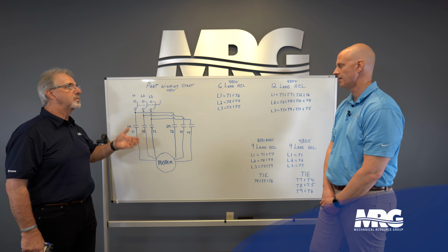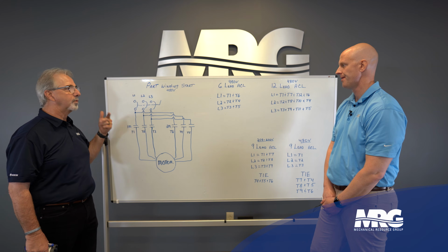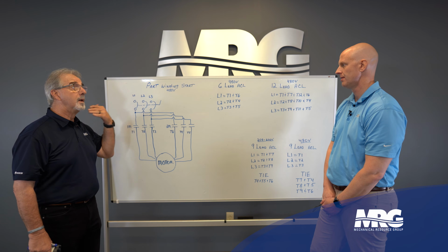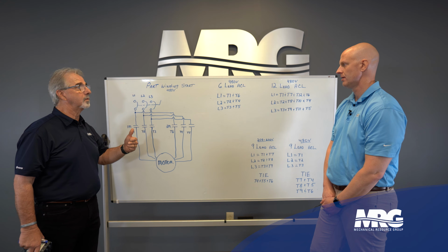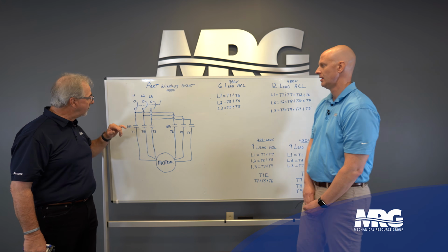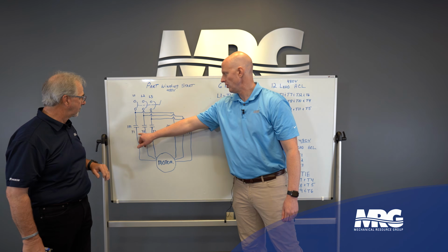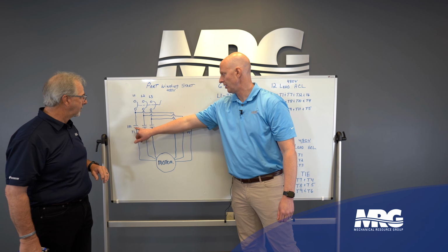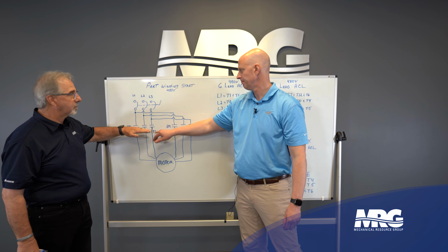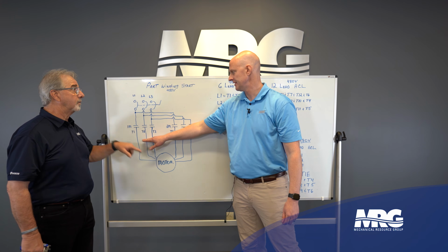So what happens, like I said, we're at 68%. When I bring the 2M contactor in, now I'm going to get full voltage to that motor, even though there's 480 here. So M1 comes on, all 3 of these close at one time. That's 68% of the motor winding.